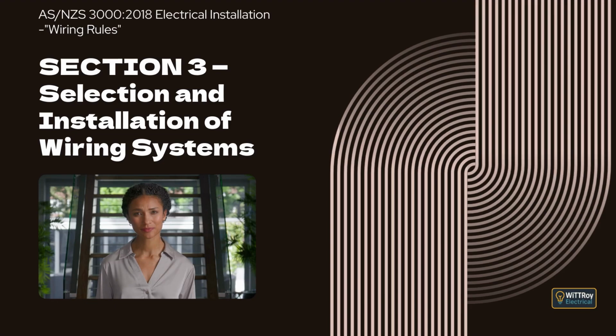Clause 3.9.7.1.2, Unprotected. This clause explains requirements for consumer mains that are not protected on the supply side. These must be constructed to minimize the risk of short-circuit and installed in accordance with additional distributor requirements. Certain wiring systems are recognized as providing adequate short-circuit risk reduction.